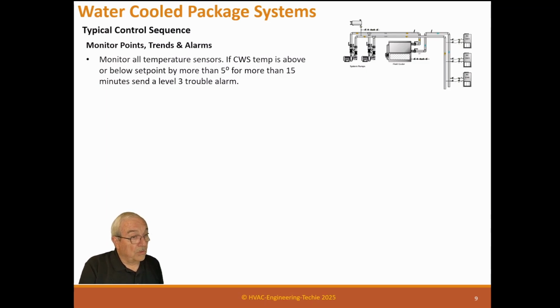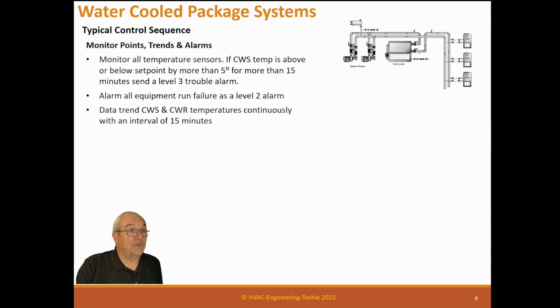It's not immediate, but he should know that it's there. A level 2 alarm is an alarm he needs to get up out of the chair and go do something about, because it needs it. A level 1 is the life safety, and a level 1 alarm should have gongs and alarms going off everywhere, and everybody needs to be concerned about a level 1. But level 3 is a trouble alarm that we need to check. And level 4 is some kind of status alarm that doesn't matter much, that you just want to log, but you don't really need to get out of your chair. Alarm all equipment run failures at a level 2 alarm. So if something fails, level 2, you need to go check what's going on.